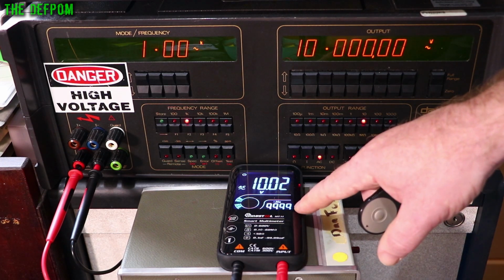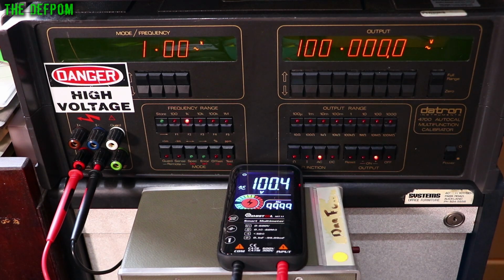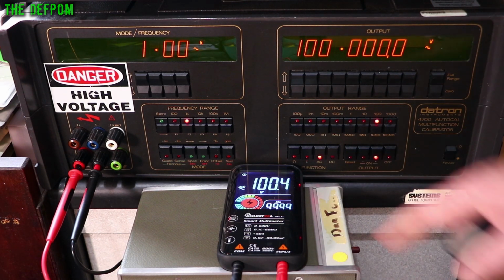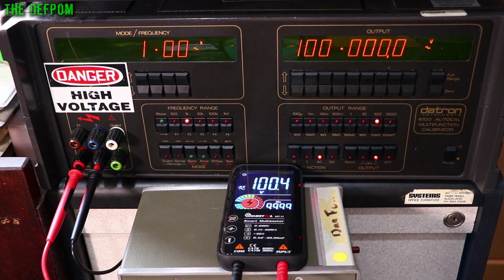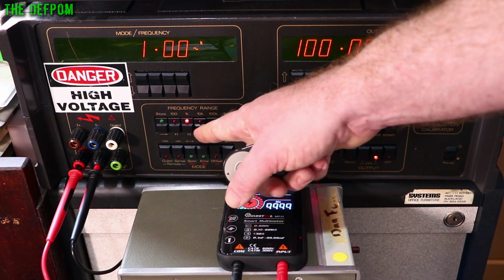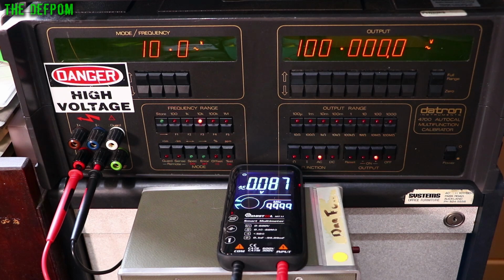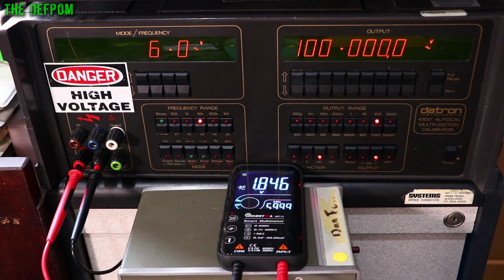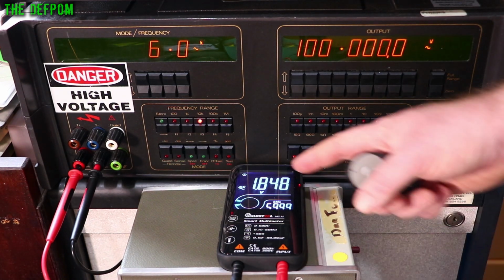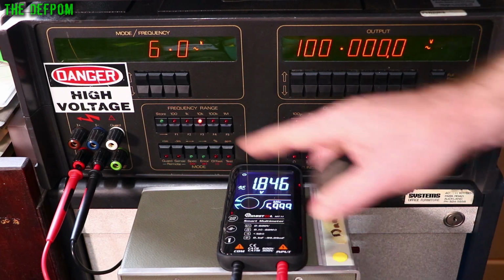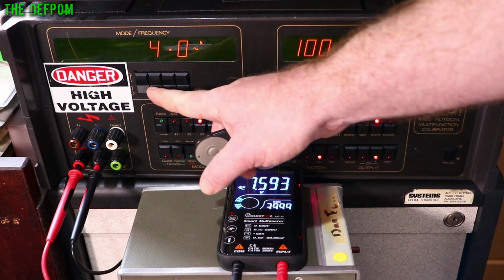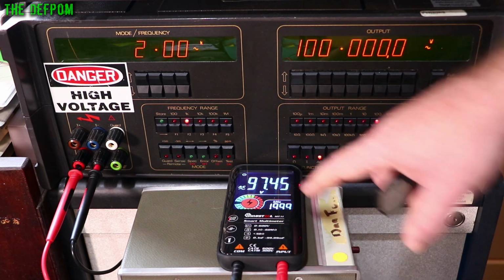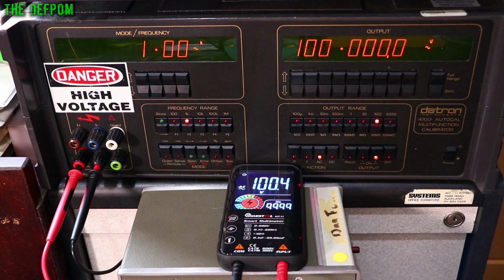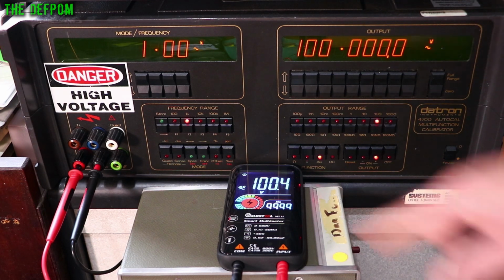It is measuring the frequency correctly as well. And 100 volts is also a few counts out there, 4 counts out. But the frequency is accurate. So let's just try this thing with the frequencies and see what's going on here. Let's try 10 kHz. And it can't read it. 6 kHz, which is what it mentions. So 1.8 volts. The frequency is correct though. Yeah, this does not like high frequency at all. So 2 kHz is out by about 3 volts. So anything above 1 kHz looks like a no-go.